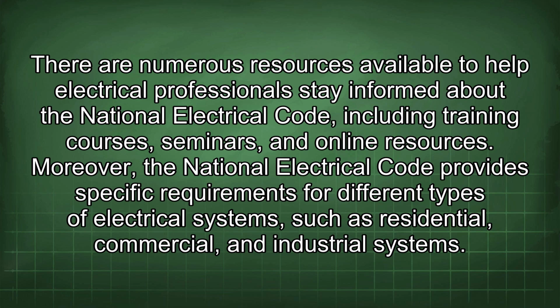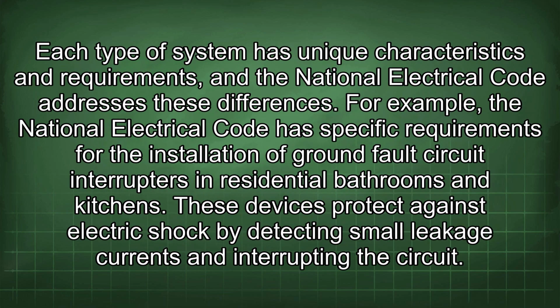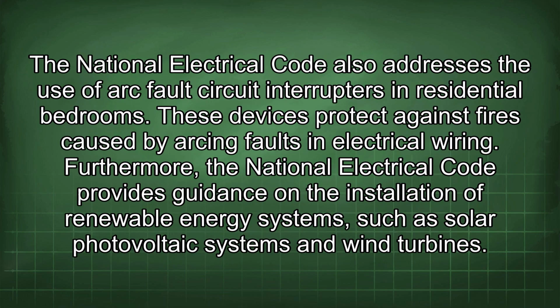Moreover, the National Electrical Code provides specific requirements for different types of electrical systems, such as residential, commercial, and industrial systems. Each type of system has unique characteristics and requirements, and the National Electrical Code addresses these differences. For example, the National Electrical Code has specific requirements for the installation of ground fault circuit interrupters in residential bathrooms and kitchens. These devices protect against electric shock by detecting small leakage currents and interrupting the circuit. The National Electrical Code also addresses the use of arc fault circuit interrupters in residential bedrooms. These devices protect against fires caused by arcing faults in electrical wiring.